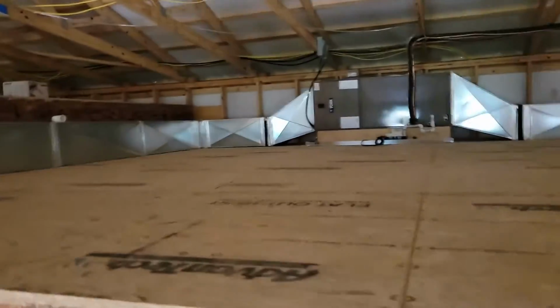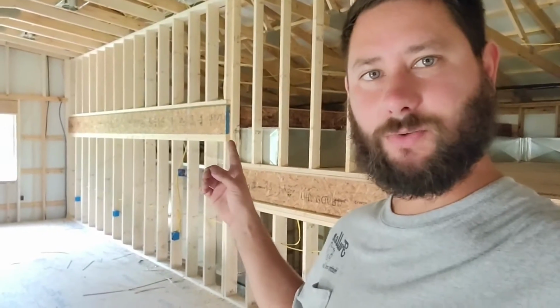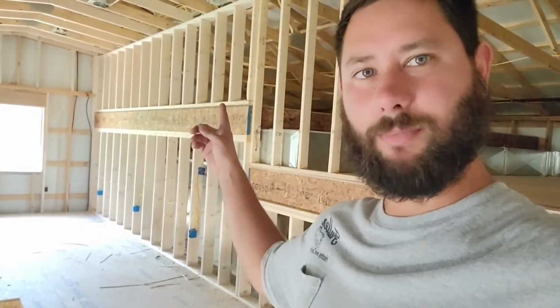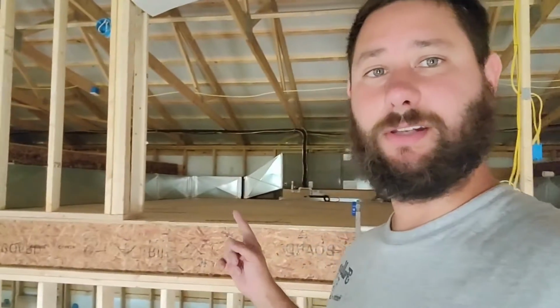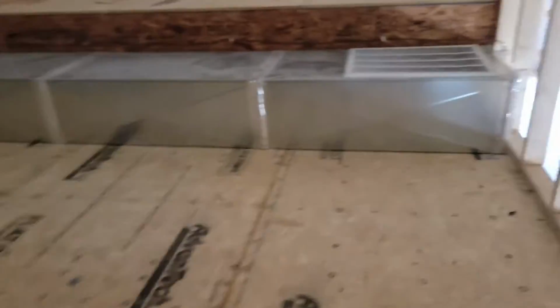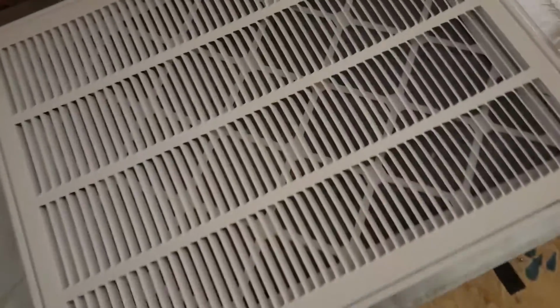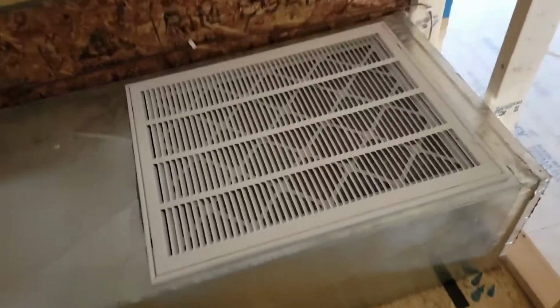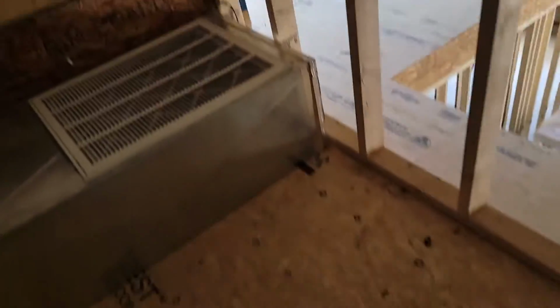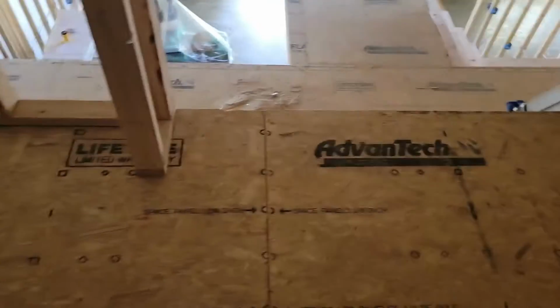Now let me show you where the return is up here. The upstairs return was going to be located right here above this truss on the wall, but I gave the customer the option to conceal it, and they went for that. But we need to make sure it still can pull from this main area. So I'm going to show you what we're going to do. Come up here. There's going to be a large access door right here. And then we put the upstairs return, 20 by 25, right here in the ductwork instead of going through the wall, which is good unless you can't pull from this area out here.